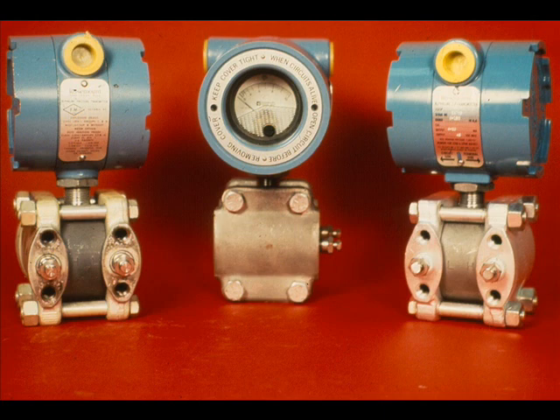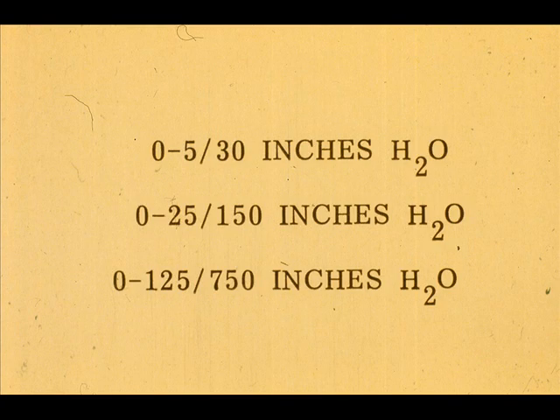The Rosemount differential pressure transmitters will measure from 0–5 to 0–750 inches of water differential. Three different sensor modules are required to cover this range. This table shows the span limits of each sensor for the differential pressure modules — note that the span rangeability is 6 to 1.